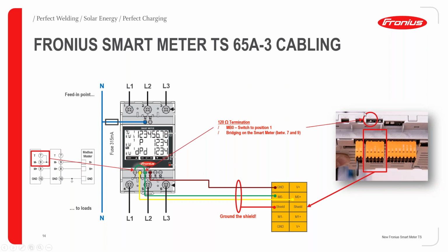In the inverter Gen 24, you will have a switch right above this orange plug. You have to put it in position 1. And in the smart meter, you have to bridge a cable between connection points 7 and 9. This way, you are enabling the terminal resistor. And then the other important thing to make sure the communication works well is to always use a twisted pair cable for the data plus and data minus. In this Gen 24, it's marked as M0 plus and M0 minus. So always use a twisted pair cable for this so that you can be sure that your connection works fine.